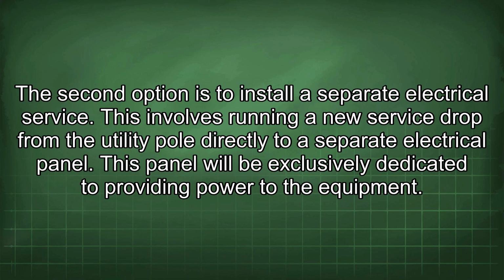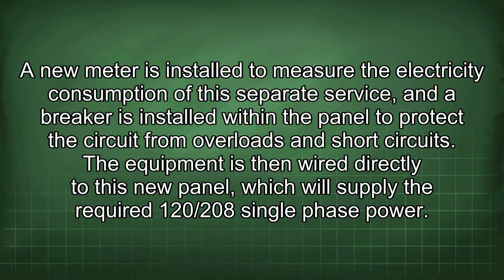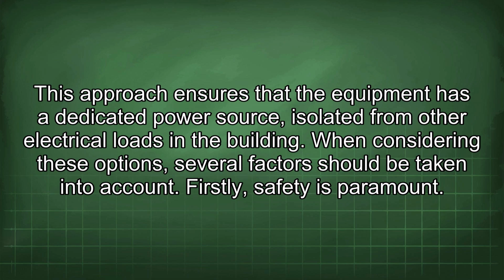This involves running a new service drop from the utility pole directly to a separate electrical panel. This panel will be exclusively dedicated to providing power to the equipment. A new meter is installed to measure the electricity consumption of the separate service, and a breaker is installed within the panel to protect the circuit from overloads and short circuits. The equipment is then wired directly to this new panel, which will supply the required 120/208 single-phase power. This approach ensures that the equipment has a dedicated power source, isolated from other electrical loads in the building. When considering these options, several factors should be taken into account.